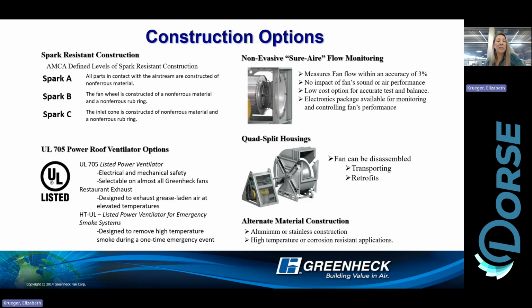But basically, Sure Air is a piezo ring that goes around the inlet cone that has ports in it that we can actually take a pressure from, and then we take a differential pressure on the outside of that fan. That differential pressure plus an area we use to calculate the airflow in the system. Test and balance can come out and hook up their transducers right to our fan, no problem. And then we have a calculation that they would use with a K factor to get the actual flow of that fan.